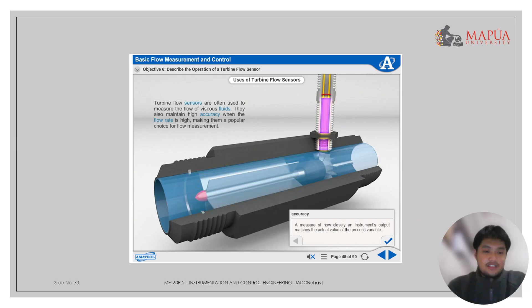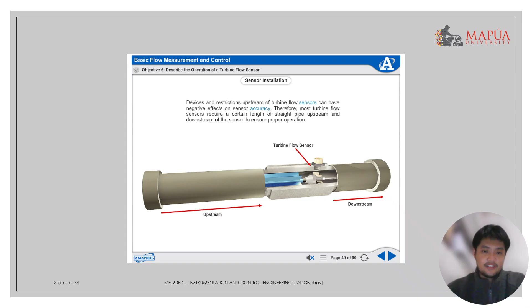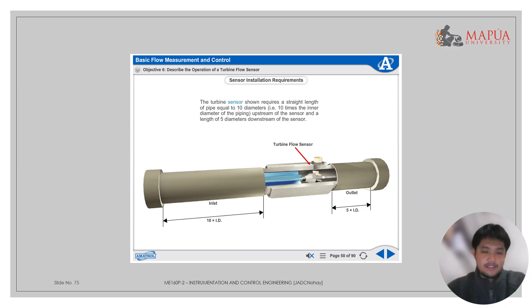Sensor installations. Devices and restrictions upstream of turbine flow sensors can have negative effects on sensor accuracy. Therefore, most turbine flow sensors require a certain length of straight pipe upstream and downstream of the sensor to ensure proper operation. The turbine sensor shown requires a straight length of pipe equal to 10 diameters upstream of the sensor and a length of 5 diameters downstream of the sensor.